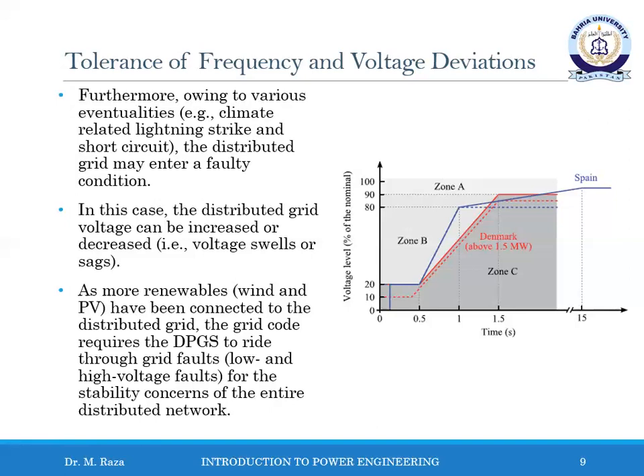In this diagram, a low voltage ride-through requirement is demonstrated for wind, which is represented by the solid line, and PV, which is shown with the dashed line. The diagram also illustrates grid codes for two different countries, that is, the blue color represents the Spanish grid code and the red color represents the Danish grid. Generally, the low voltage ride-through requirements can be divided into three zones, such as Zone A, Zone B, and Zone C. In Zone A, the distribution power generation system should remain connected to the distribution grid and maintain the power production.